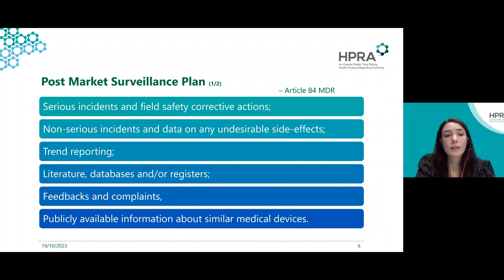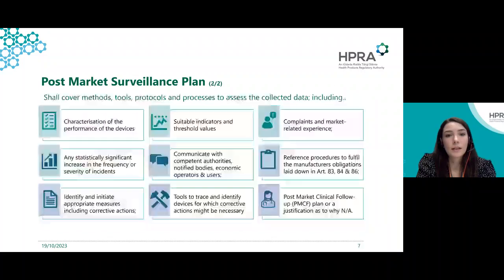So the data collected under a post-market surveillance system helps address important questions on the safety and performance of a device and often results in improvements in the device design and manufacture. And just continuing on then, the post-market surveillance plan should also detail methods and tools, protocols, processes to assess the data. So it should allow correct characterization of the performance of the devices and a comparison to similar other products on the market. It should have suitable indicators and threshold values to allow continuous reassessment of the benefit risk analysis and risk management. It should set out methods to investigate complaints and analyze market-related experience collected in the field.